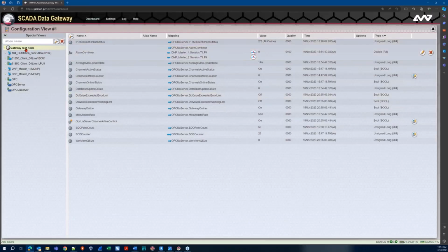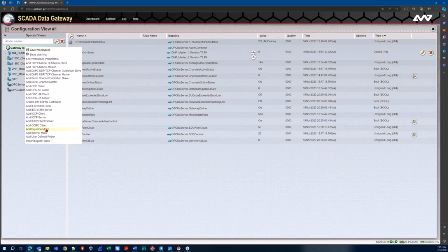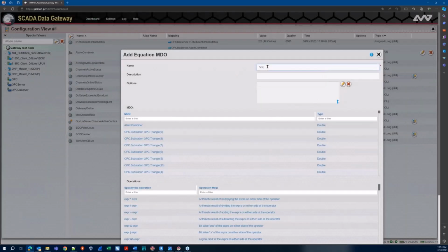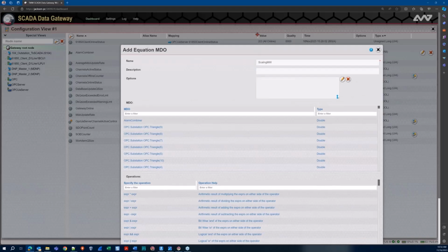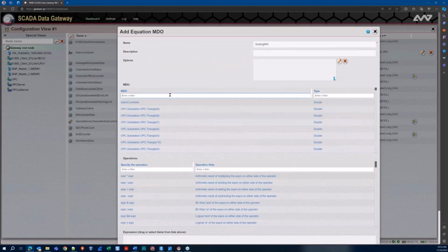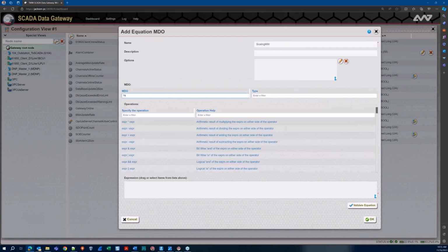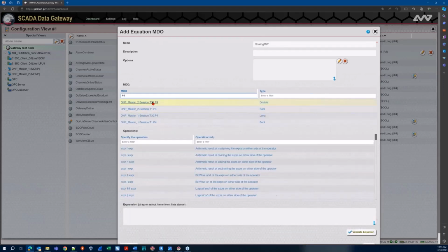Let's say I might want another example of the type of equation you could do. Maybe I want to do some scaling. I want to convert my kilowatts, for example, that's coming into - I believe this is also P4, in type 30, which is my analog inputs. So this is my kilowatts value passing through a specific breaker. I could just take that, divide it by 1,000, and that'll let me know how many megawatts I have passing through this device as opposed to the kilowatts I'm getting. Again, just a basic example, but to give you an idea of what's possible using equations.